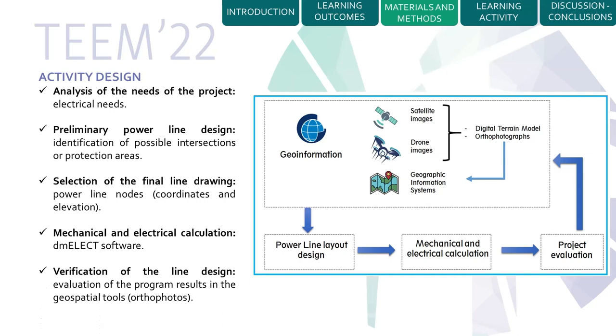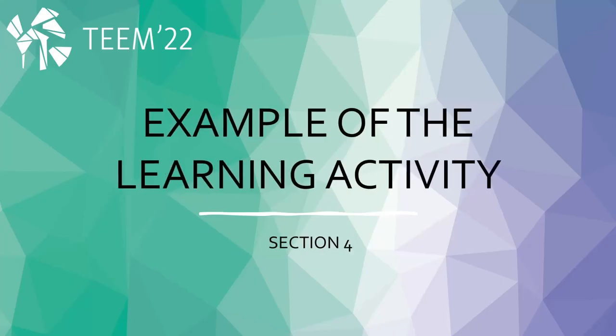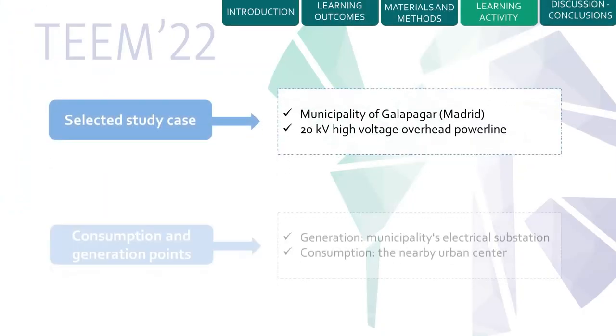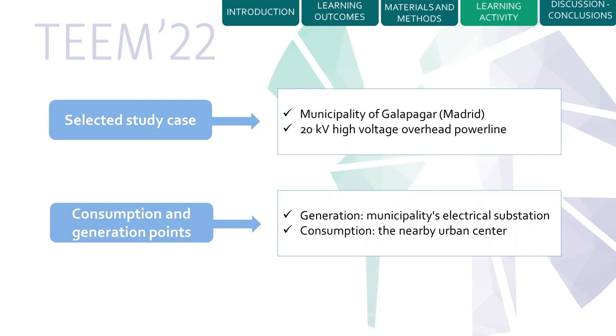Finally, we will have the power line layout designed, so we will perform the mechanical and electrical calculations with specific software, and the final project evaluation. As an example of this proposed activity, we have selected the Municipality of Galapagar in Madrid, a 20kV high voltage overhead power line, and we have calculated the generation and consumption points.